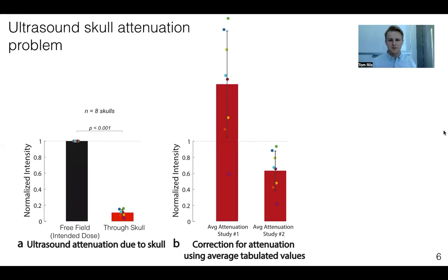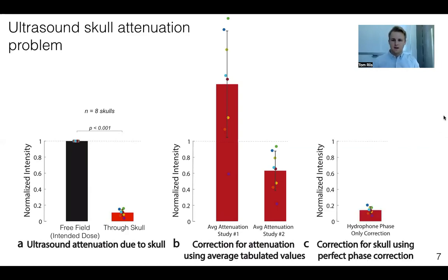Another approach that we might take would be to use CT phase corrections for the skull, which is used in these high-intensity focused ultrasound ablations of brain tissue. This plot here is showing the intensity at target through the skull with a perfect phase correction taken with hydrophone phase correction values. And what we see is that even with the best case scenario, we really only recover 15% of the intensity at target. And this is really because the reduction in intensity through the skull is mostly due to the attenuation of the ultrasound rather than dephasing of the ultrasound beams.